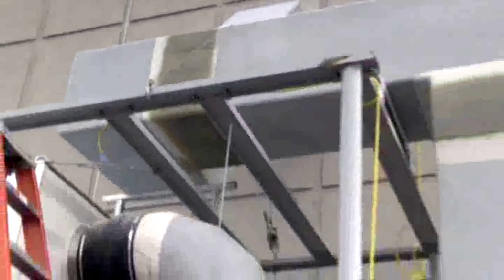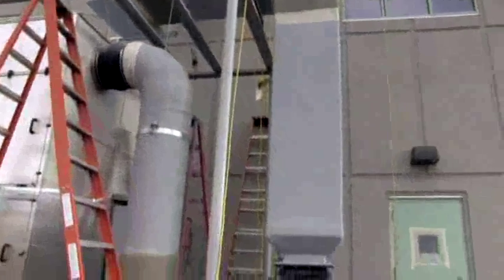This is an odor control system. It's kind of state-of-the-art. It's technology that comes from Germany. It's photoionization. It uses ultraviolet light and carbon filters to do that. Since this has been made, we have that in operation, and it's been very effective. The wastewater that comes into the plant is actually pretty corrosive, with hydrogen sulfide gas that can be pretty corrosive, so it all has to be high-quality stainless steel or fiberglass.